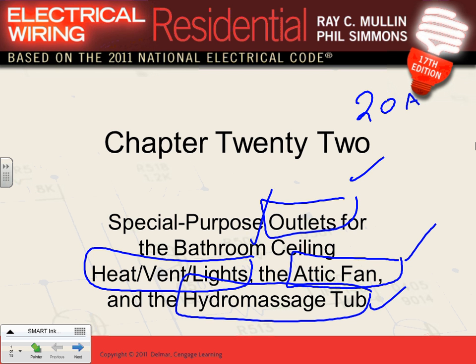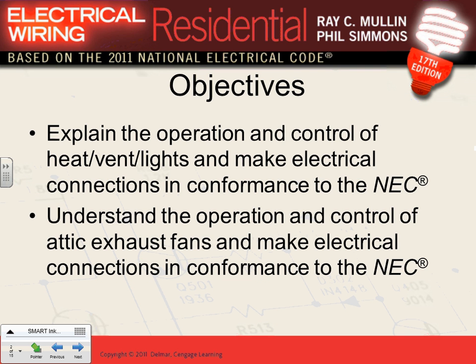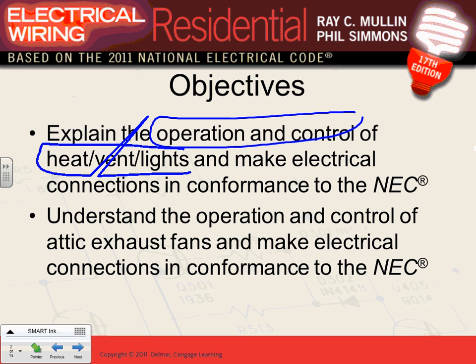How many 20 amp circuits do I need in this case, based on the code? Four 20 amp circuits for these locations. Cool? With a 20 amp circuit goes 12-2, right? 12-2 conductor. Okay, so that's basically what we're going to be doing. A few things about operation and control of this special fixture that they call a heat vent light fixture. You can look at this in a second here.